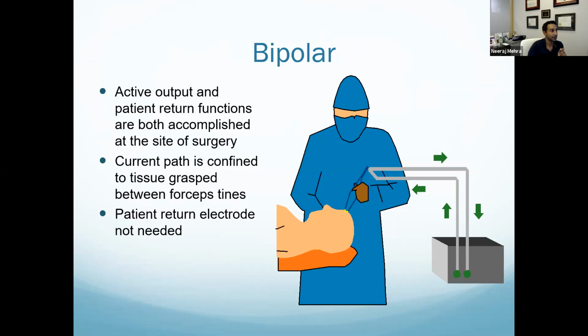Now, in open surgery, for a lot of what we do in gynecology and obstetrics, we don't use much bipolar energy. But if you were to use bipolar energy, the reason it's called bipolar is that you have the electrosurgical unit, which gets to your active electrode, and your active electrode has two poles. It has a positive and a negative. So it goes from one side to the other side, comes back through the active electrode, and then back to your generator. So the patient is not involved in the circuit.